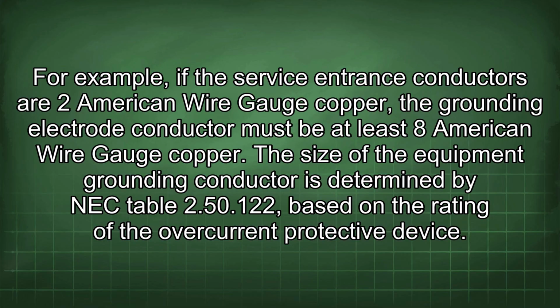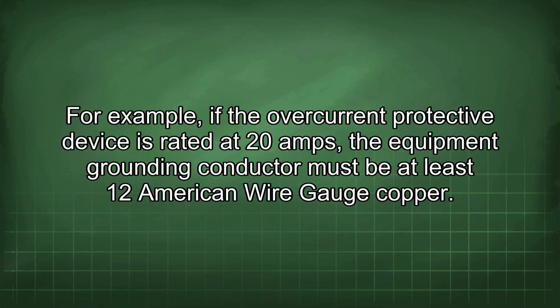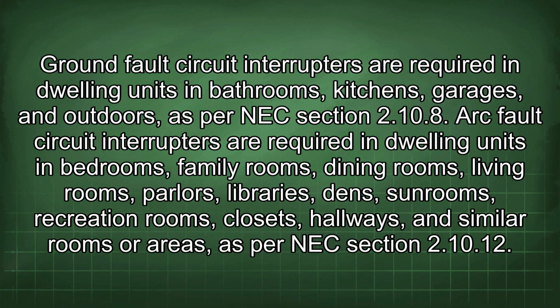The size of the equipment grounding conductor is determined by NEC Table 250.122 based on the rating of the overcurrent protective device. For example, if the overcurrent protective device is rated at 20 amps, the equipment grounding conductor must be at least 12 American wire gauge copper. Ground fault circuit interrupters are required in dwelling units in bathrooms, kitchens, garages, and outdoors, as per NEC Section 2.10.8.